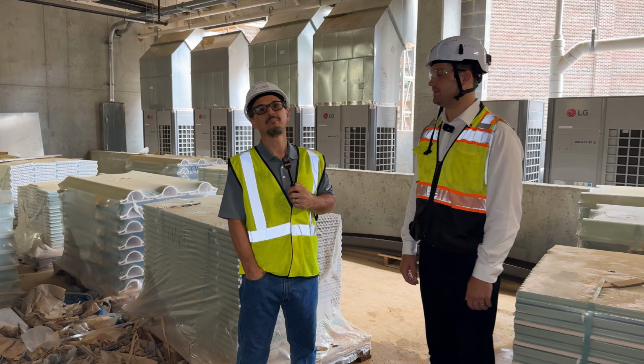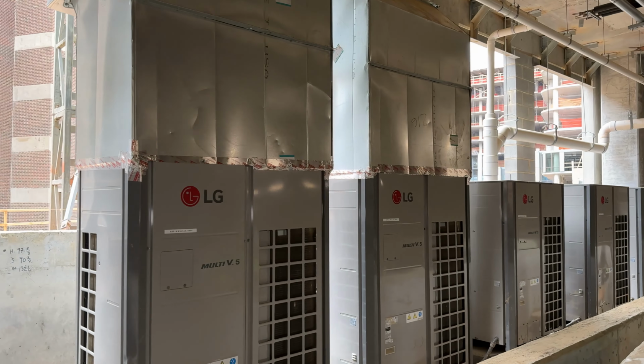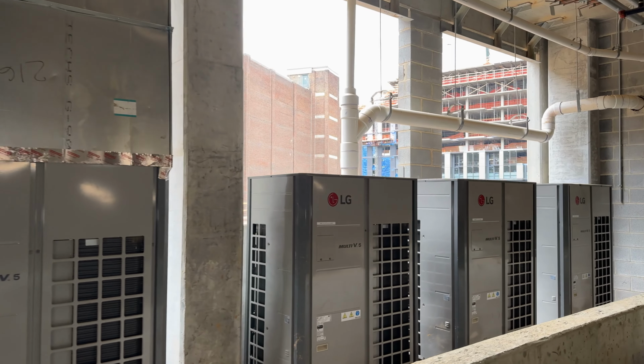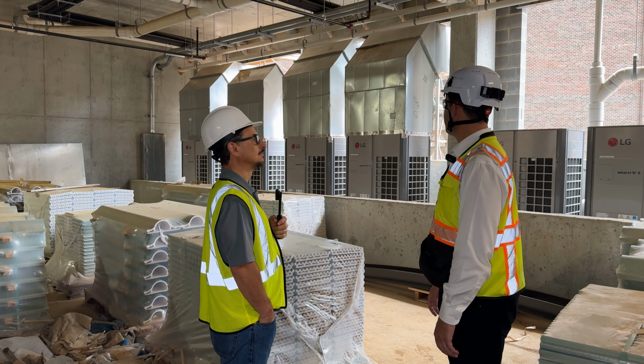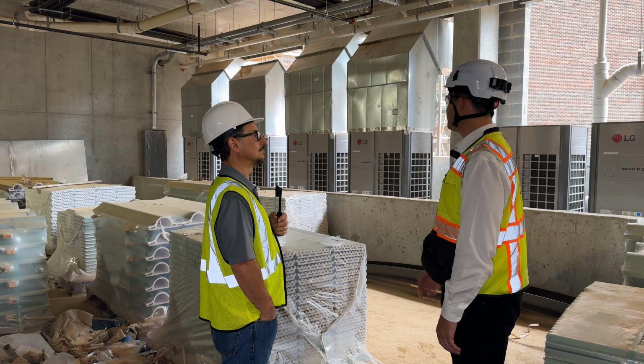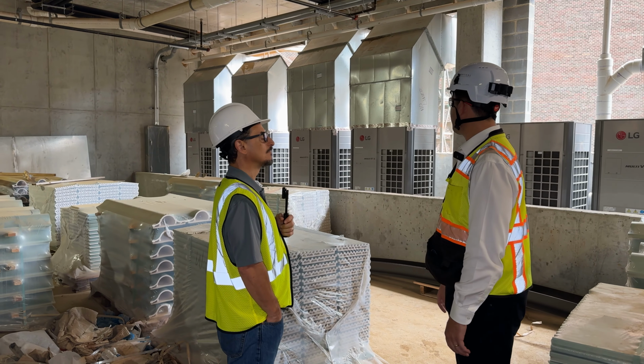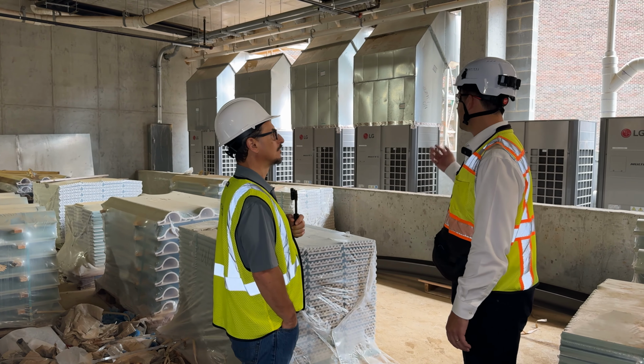Yep. You'll see the ducted air-cooled units, though not very common. This is an application where it made sense to use the air-cooled VRF condensers. Just duct them to a louver. Yep. So you can actually modify the static pressure setting on the discharge fan to allow this application.